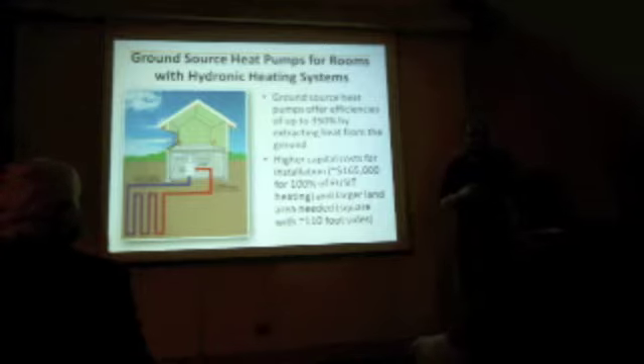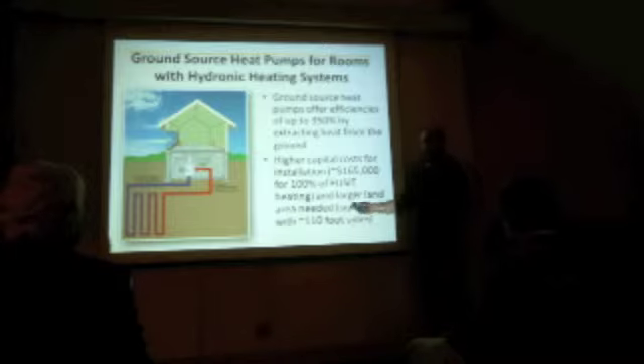I'm sorry? Yeah, and that's the question. We don't have space. We looked at this number. Yeah, no, absolutely. And it's this number at the bottom here that causes the problem for ground source. You'd need an area of at least 110 feet by 110 feet in order to drill all those wells. The wells have to be spaced about 20 feet on center. And so unless you were to acquire a parking lot or something nearby, it would be very difficult with your current configuration to find enough space to get a sizable fraction from geothermal.